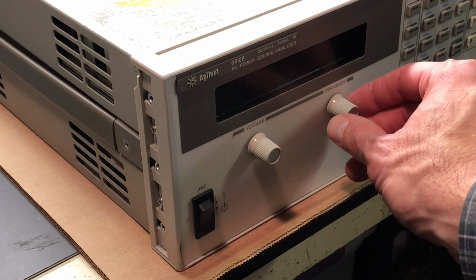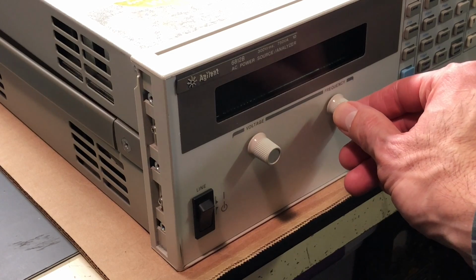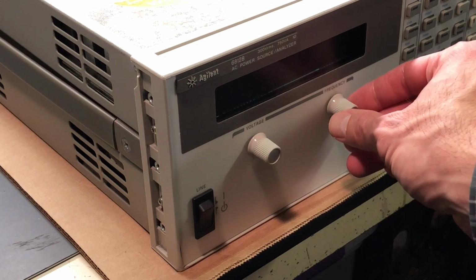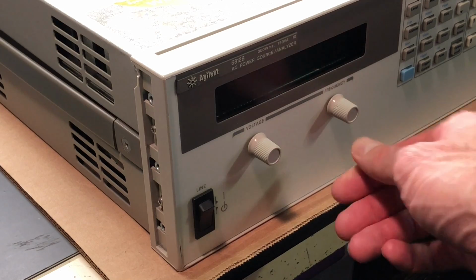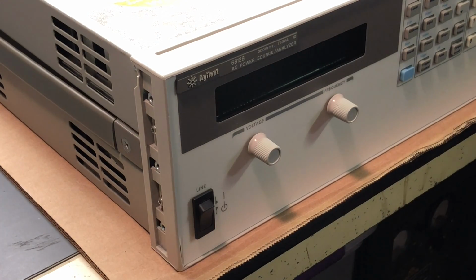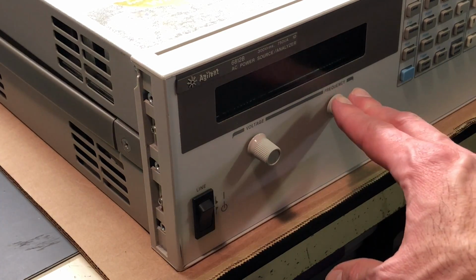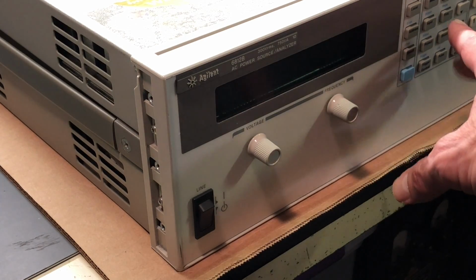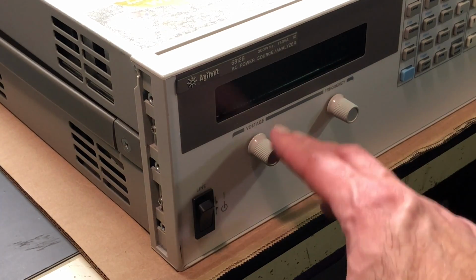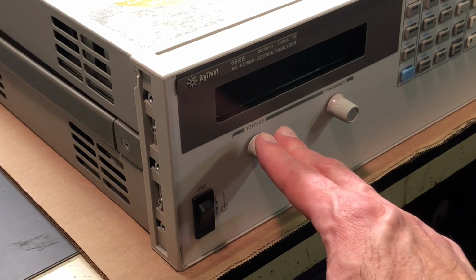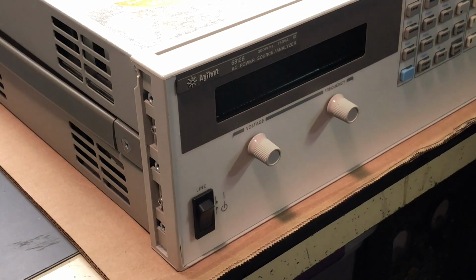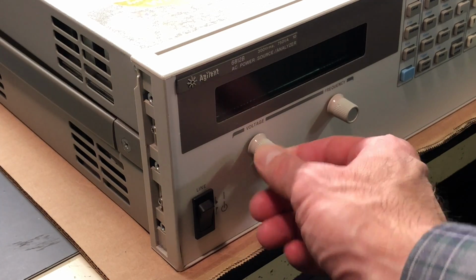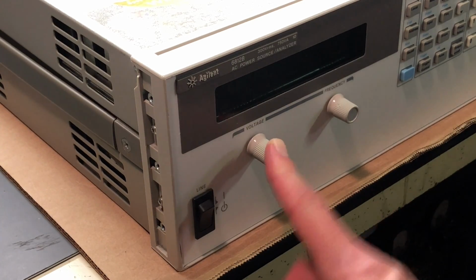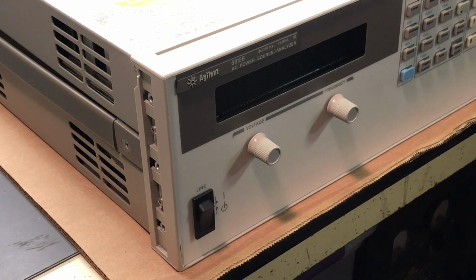Now these rotary encoders work so that when you rotate them slowly, the value increases slowly, and then as you rotate them faster, it increases the value proportionally quicker. This voltage and the frequency controls over here can also be entered directly by the keypad over here. So in the worst case, if this control didn't work, you still would be able to change the voltage by entering it over on the keypad. But of course it would be nice to make this work, so I have to take a closer look at this. Now there's also an issue on the back panel, so we'll take a look at that next, and then I'll take the top cover off and we'll start to investigate inside and see what the condition is.